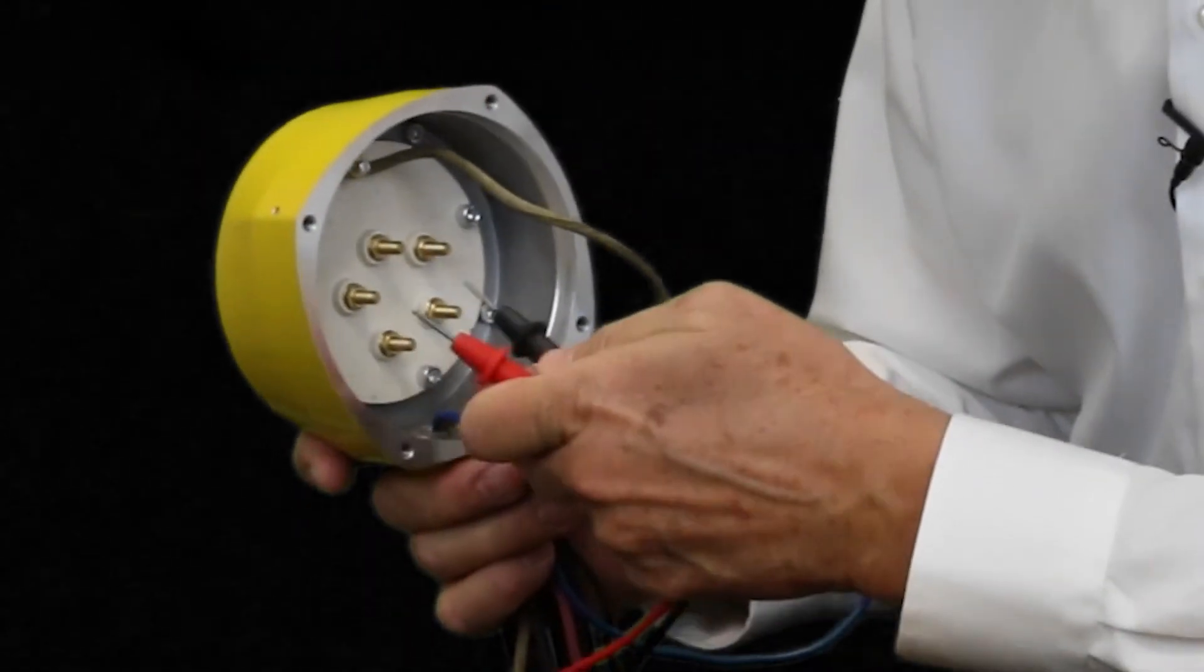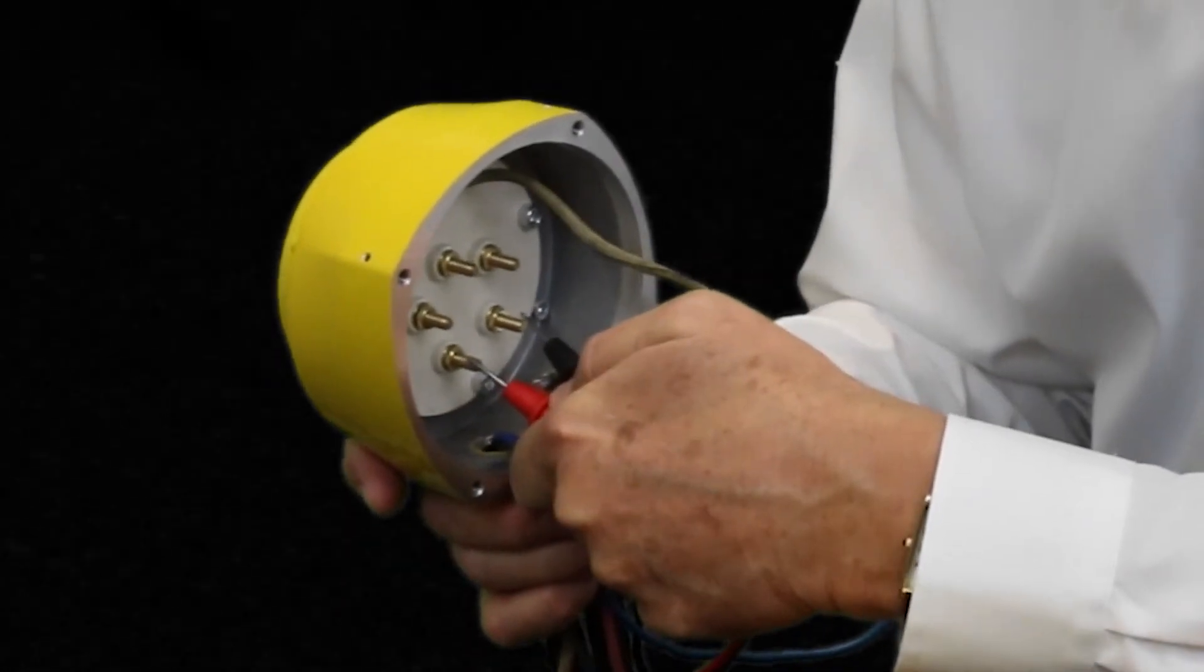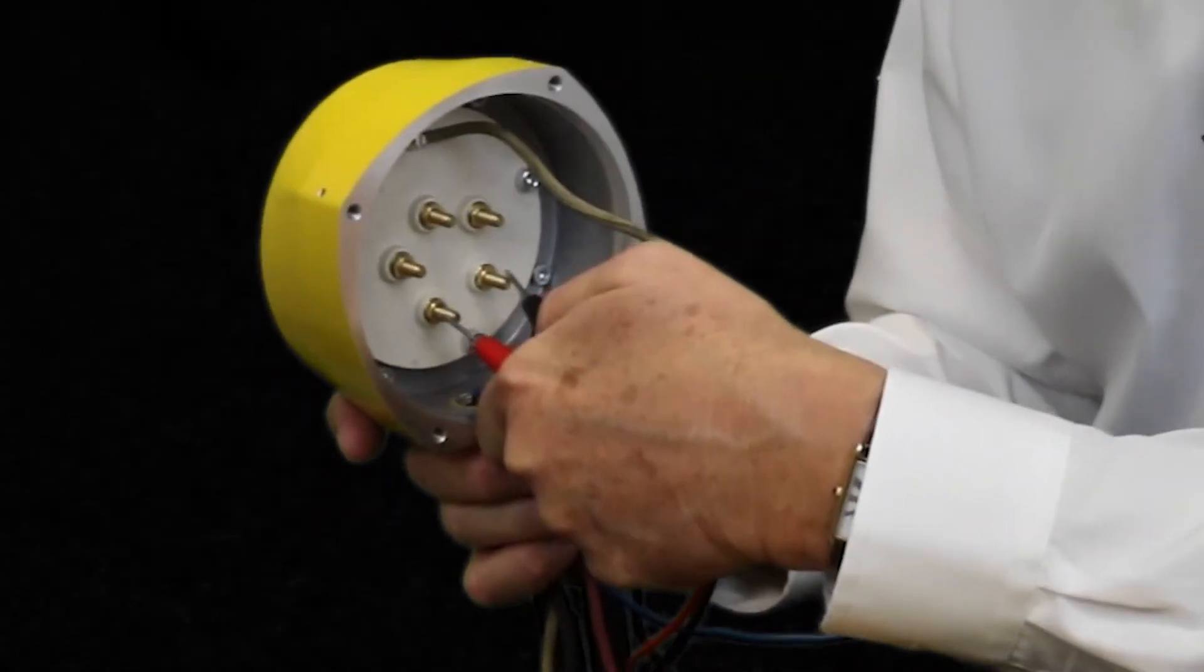To check the resistance across the thermal protection switches, we put the probes across terminals T1 and T2.